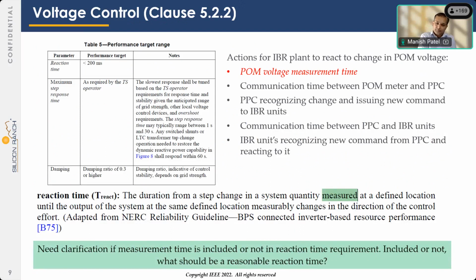All right, so then this has also gotten some attention in the industry. When you're doing voltage control, the standard goes into performance requirements. It states that the reaction time shall be less than 200 milliseconds. Step response time could be anywhere between 1 second and 30 seconds, and this is usually specified by the transmission entity, and the damping ratio of 0.3 or better, right? So then when we think about how to meet this reaction time requirement of less than 200 milliseconds, this is all we need to think about.